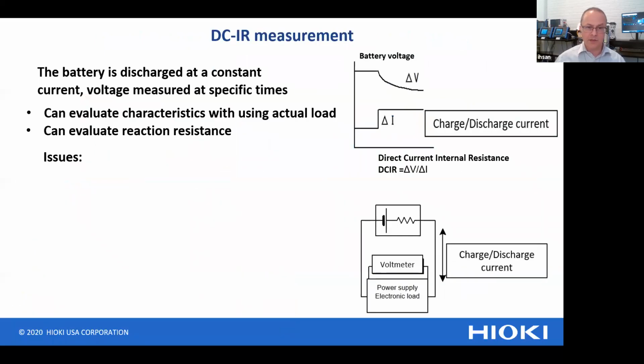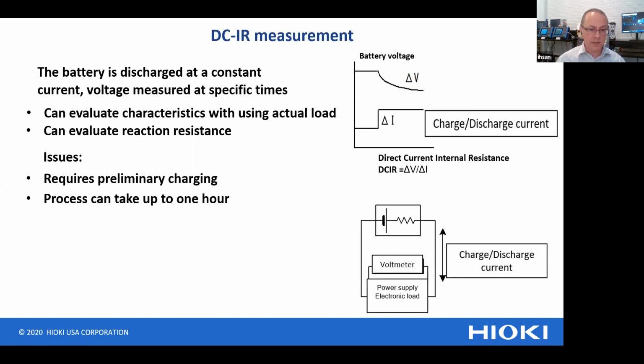There's 2 main methods of measuring the internal resistance of a battery. The first method is the DC-IR measurement. This is where the battery is discharged at a constant current and voltage is measured at specific times. The benefits of the DC-IR measurement is that it can evaluate characteristics using an actual load and can evaluate reaction resistance. Some of the issues with it, obviously, is that it requires preliminary charging of the cells. And that process can take up to an hour depending on the capacity of the cell.